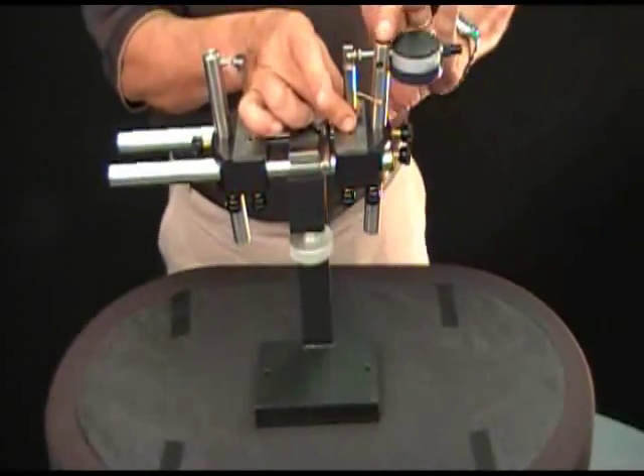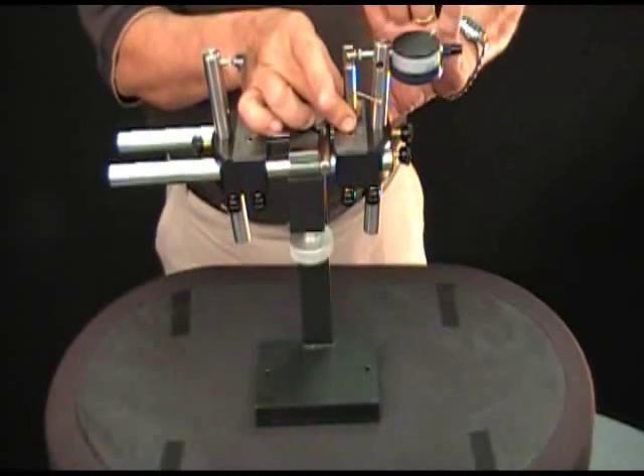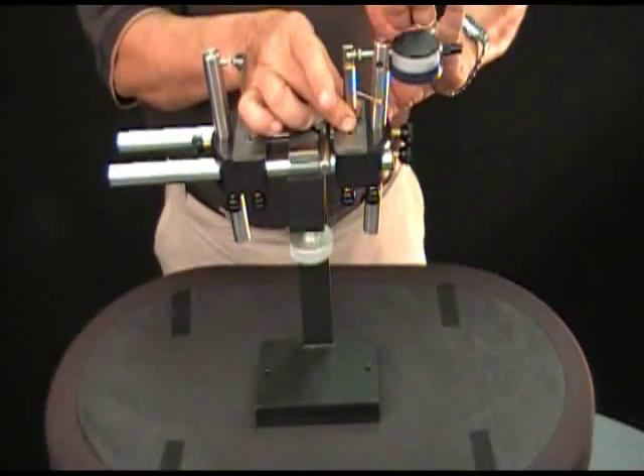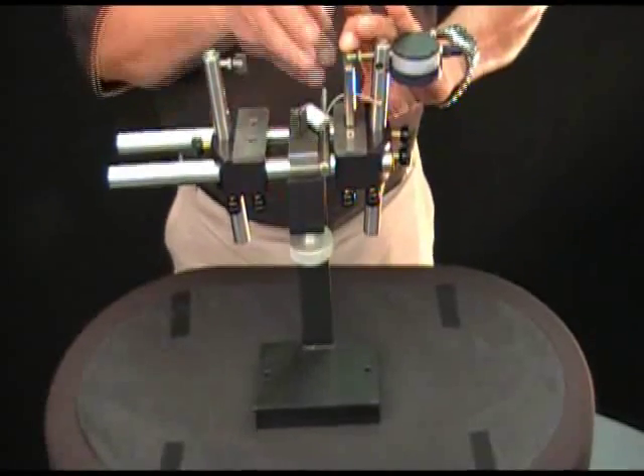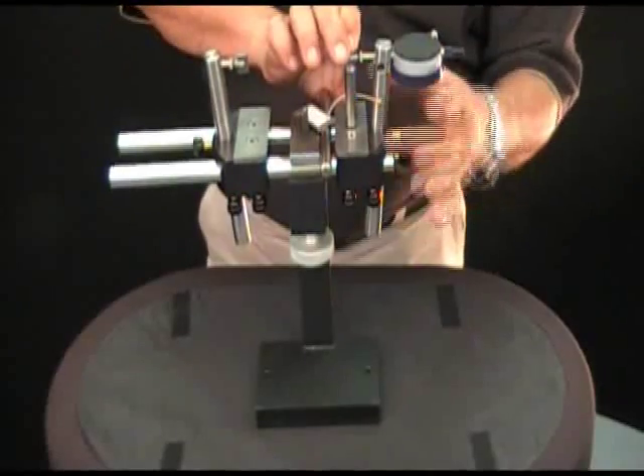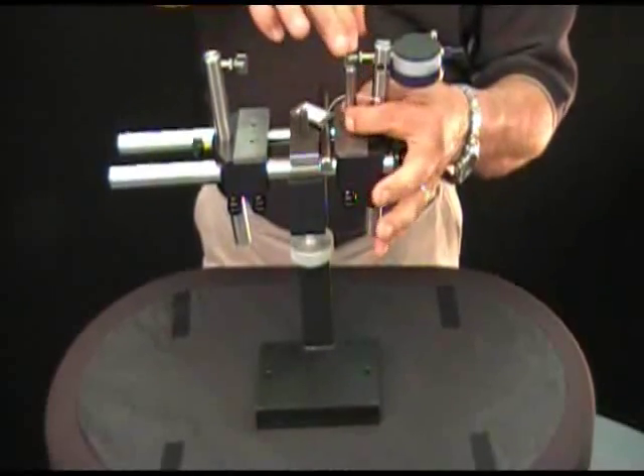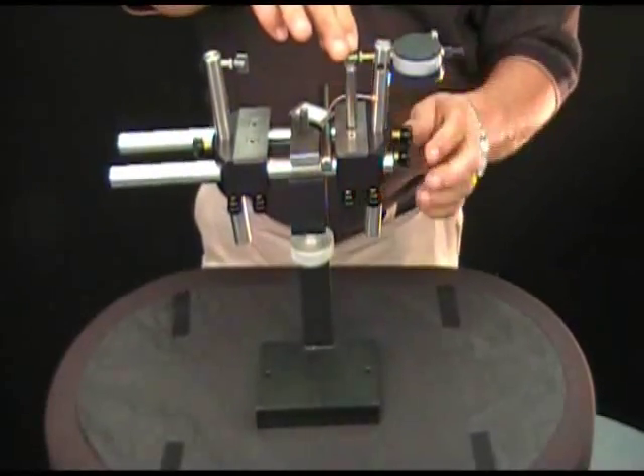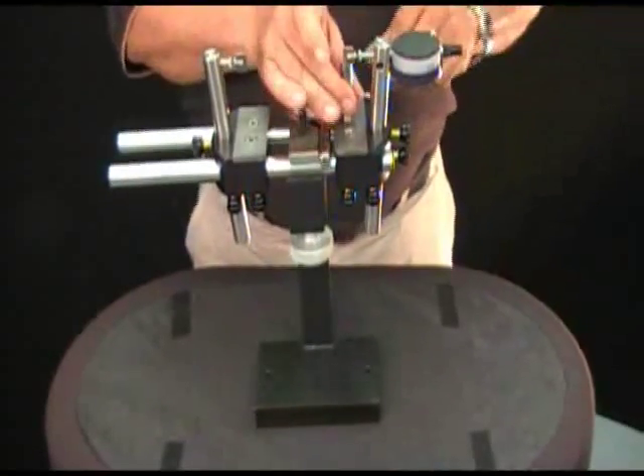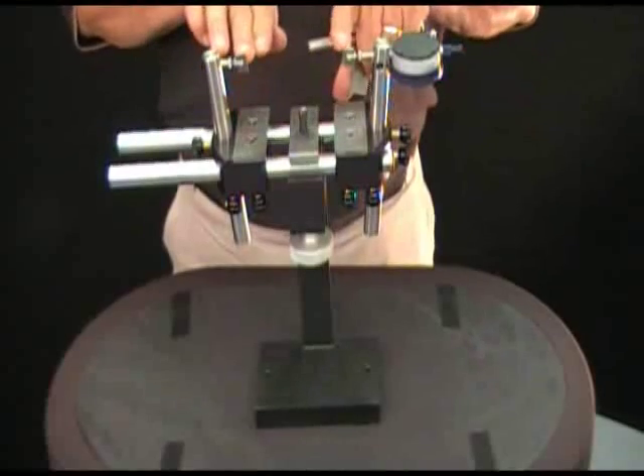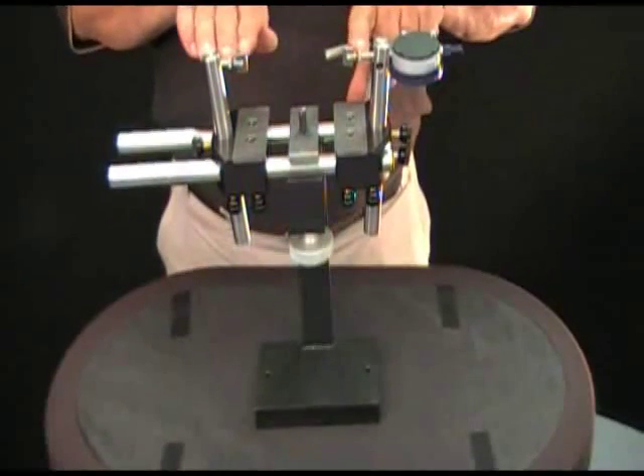The tendency is going to want to pinch using the upper arm, but that could apply a bending moment to that stem. So I always like pushing down on the shoe and then locking my knobs. I rotate my shoe, my standard side to side to make sure it's parallel with the wear pad. Continue to tighten. So now I have set both gauges out to the pitch diameter plane.